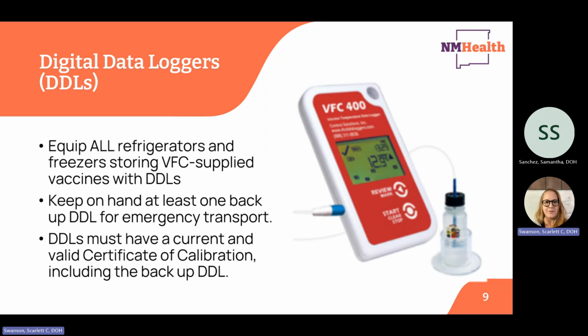The digital data logger must have an audible or visual out of range temperature alarm, a logging interval of 30 minutes or less, a low battery indicator, and a memory storage of 4,000 readings or more. A battery source is required for backup devices used during vaccine transport. Data loggers, including backup devices, must be able to generate a summary report of recorded temperature data since the device was last reset. Summary reports must include minimum and maximum temperatures, total time out of range, if any, and alarm settings. Keep on hand at least one backup battery-operated data logger for emergency vaccine transport.